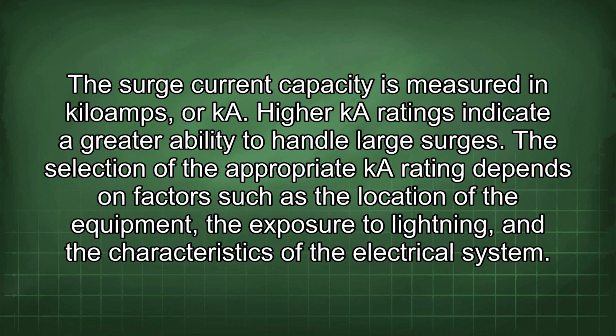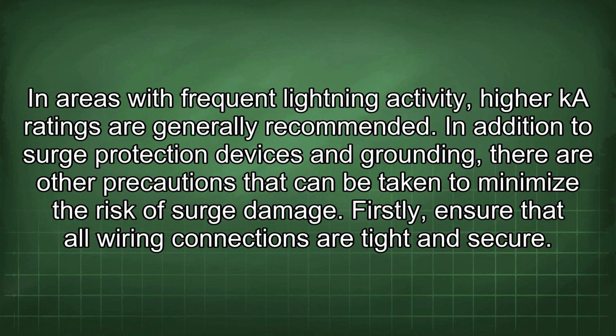The surge current capacity is measured in kiloamps, or kA. High kA ratings indicate a greater ability to handle large surges. The selection of the appropriate kA rating depends on factors such as the location of the equipment, the exposure to lightning, and the characteristics of the electrical system. In areas with frequent lightning activity, higher kA ratings are generally recommended.